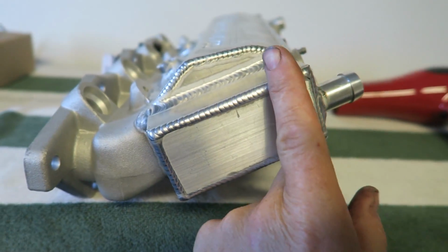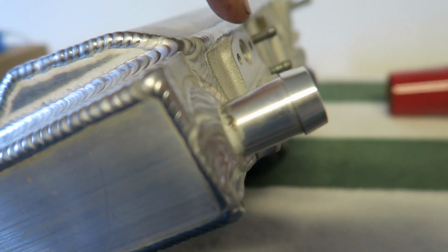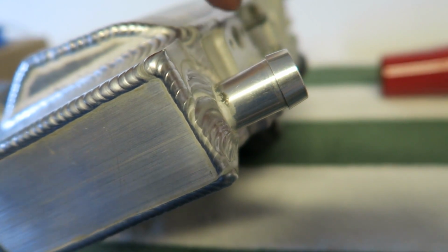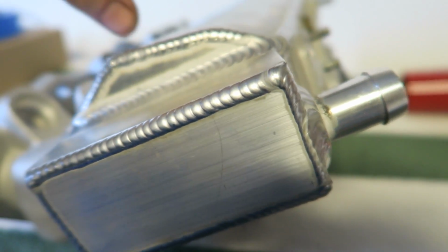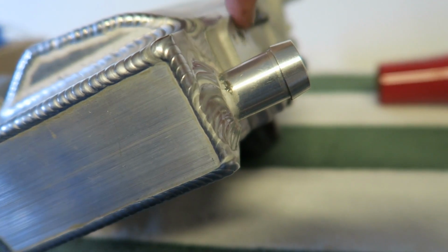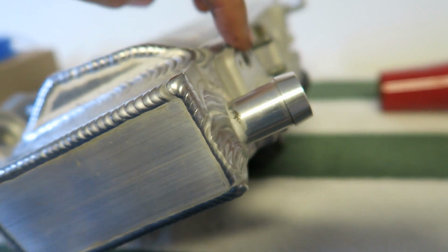If you think about how this system works, the heat is coming up here and making a turn. You're measuring on this port right here, so you're only seeing half of the core. You've got two cores right here, so you're only measuring the temperature drop on half of one core.